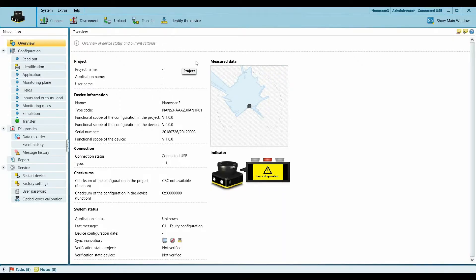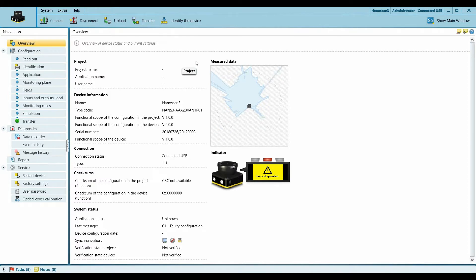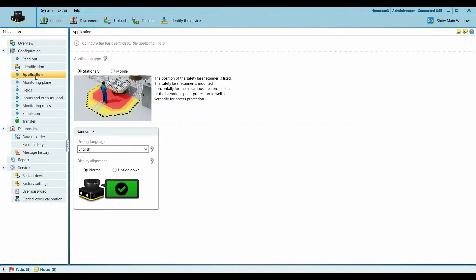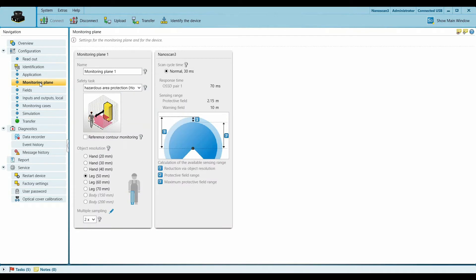So I have the Nanoscan 3 hooked up to my computer and I'm using Safety Designer software to configure the scanner. Firstly we go to Identification, where we can define the name of the device as well as a project name. Then in Application you can define if it is a stationary or a mobile application, and further we move to monitoring plane.